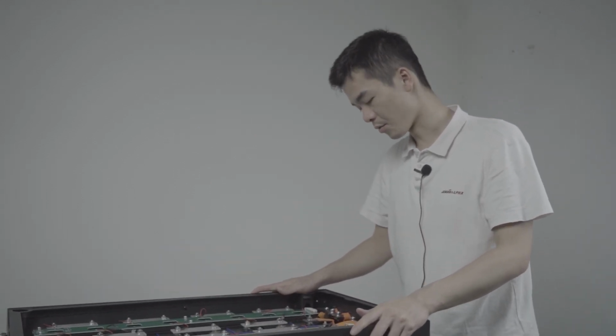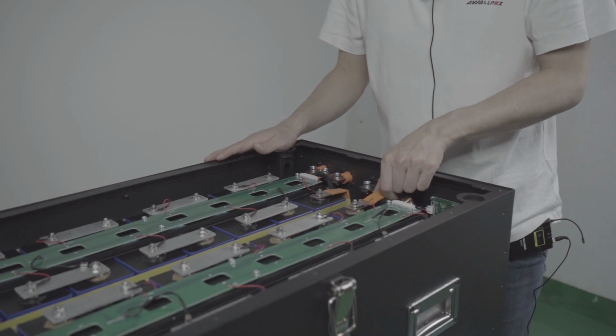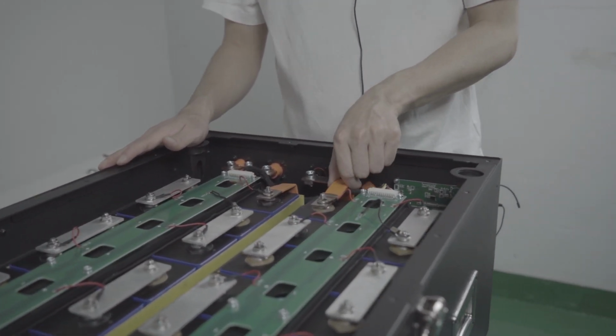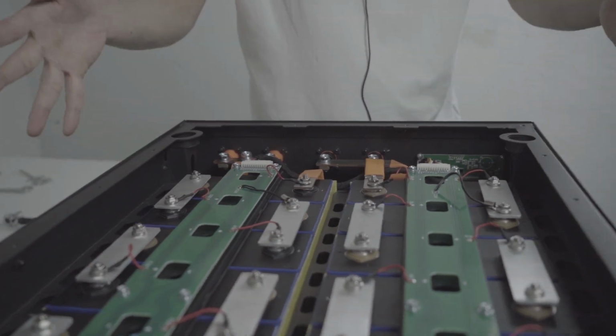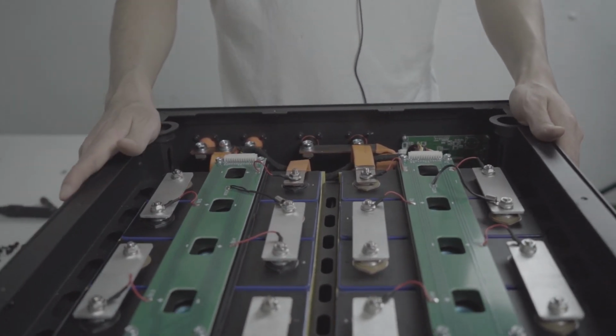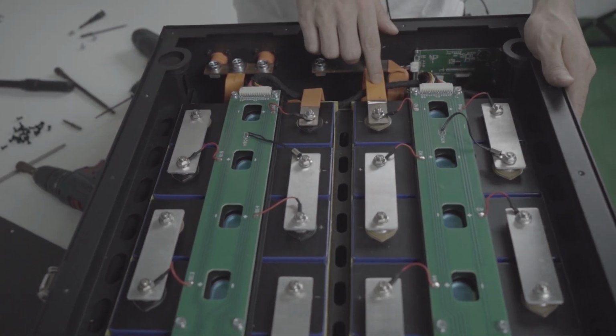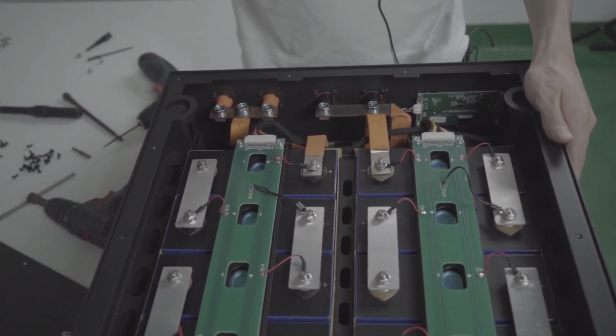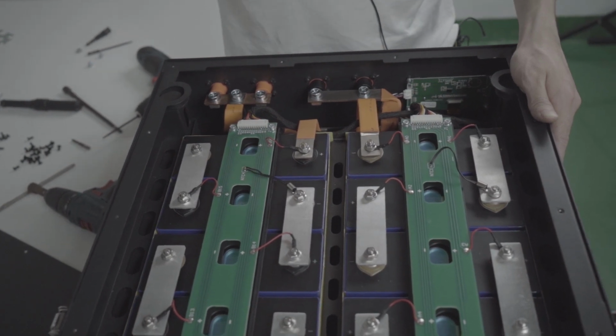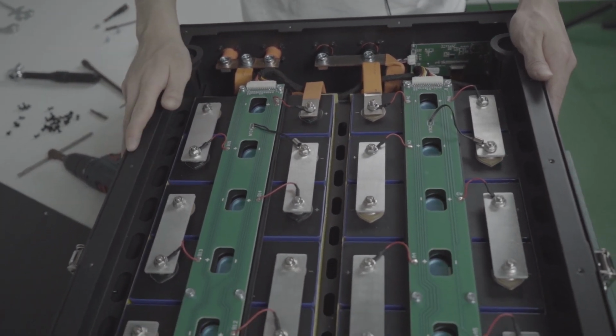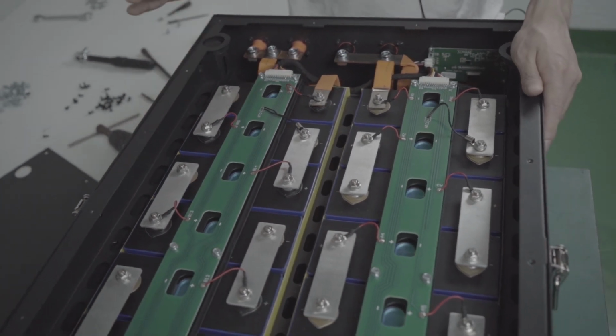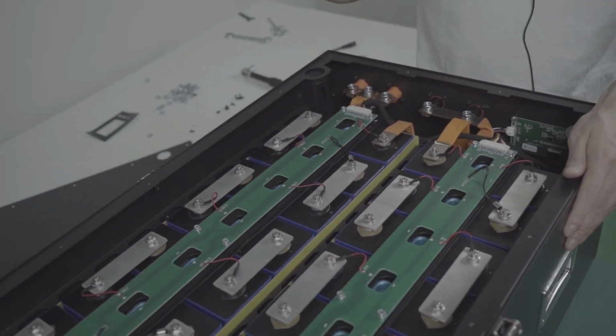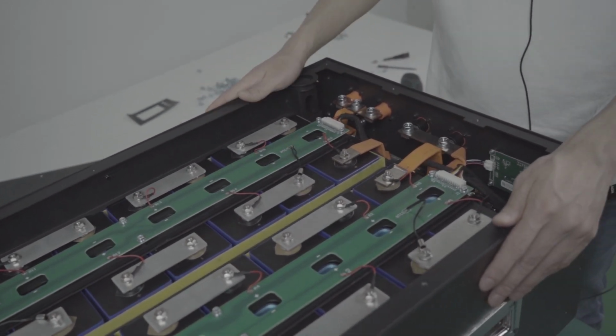After all the assembling, nearly done, you need to check if the copper bus bars, when you twitch them a little bit, are firm, because this is a big battery and the current is really great. If the copper bus bar is a little loose, the temperature may rise and the battery lifespan may be shortened. So I suggest you check them maybe twice or 3 times, as many as possible.